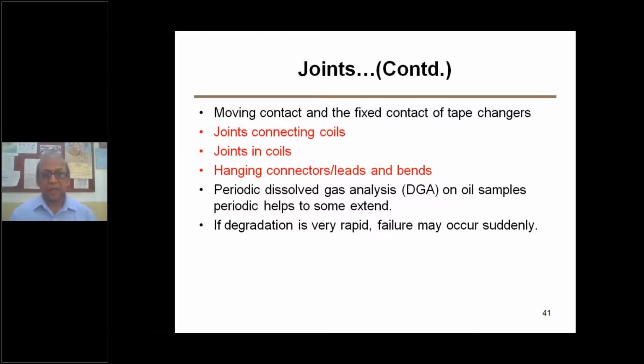Hanging connectors, leads and bends. See, if you have termination leads without proper support, it means what? There will be vibration. When there is vibration, these vibrations cause fatigue. They cause many other problems. Over there, the insulation is going to be damaged, and there is no cost. You must provide proper support to the hanging connectors and leads, and you should avoid bends. Wherever you bend, there is a chance of more fatigue. This must be avoided. This is very important. There is no cost.